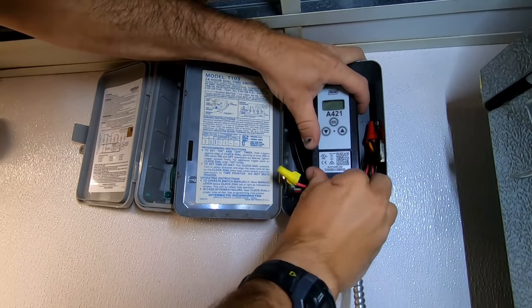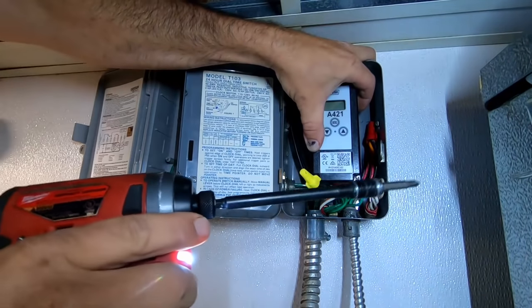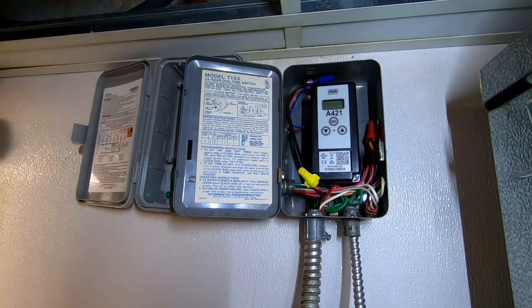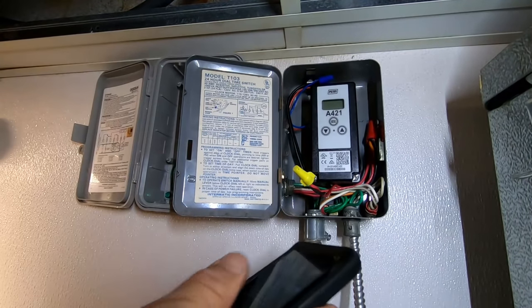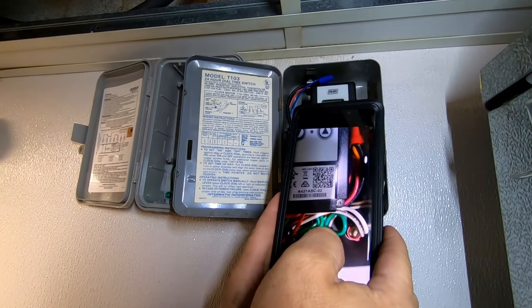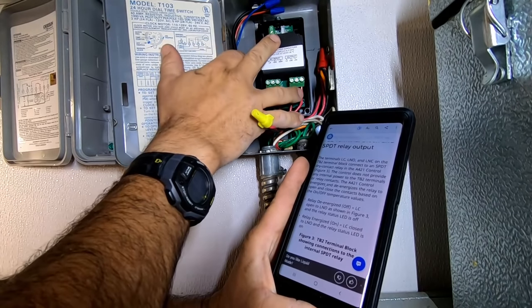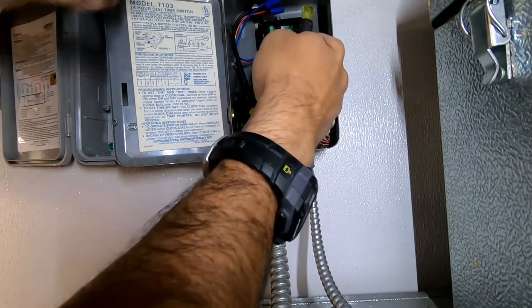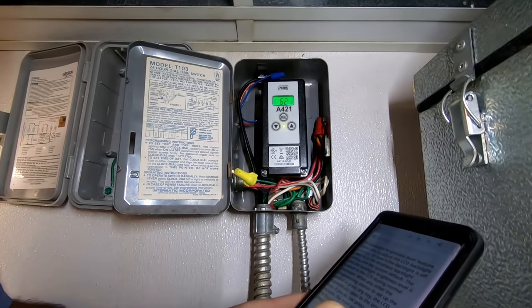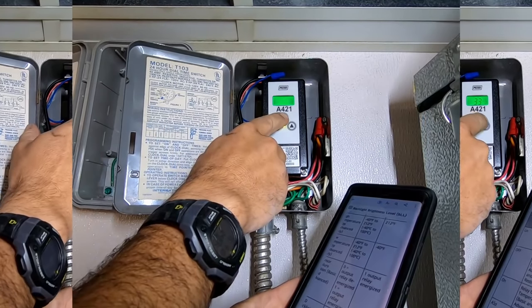Probably got that right. I'm going to see if that does scan in. Looks like that's normally open, normally closed — and they put an L in front of it. It should be normally open. I wonder if that came undone and fell over to it. Let's fix that, because that probably is not going to help. I just heard it kick on, so it must have worked. So they want it off at 33 and on at 38 — there really isn't much to set in this thing.